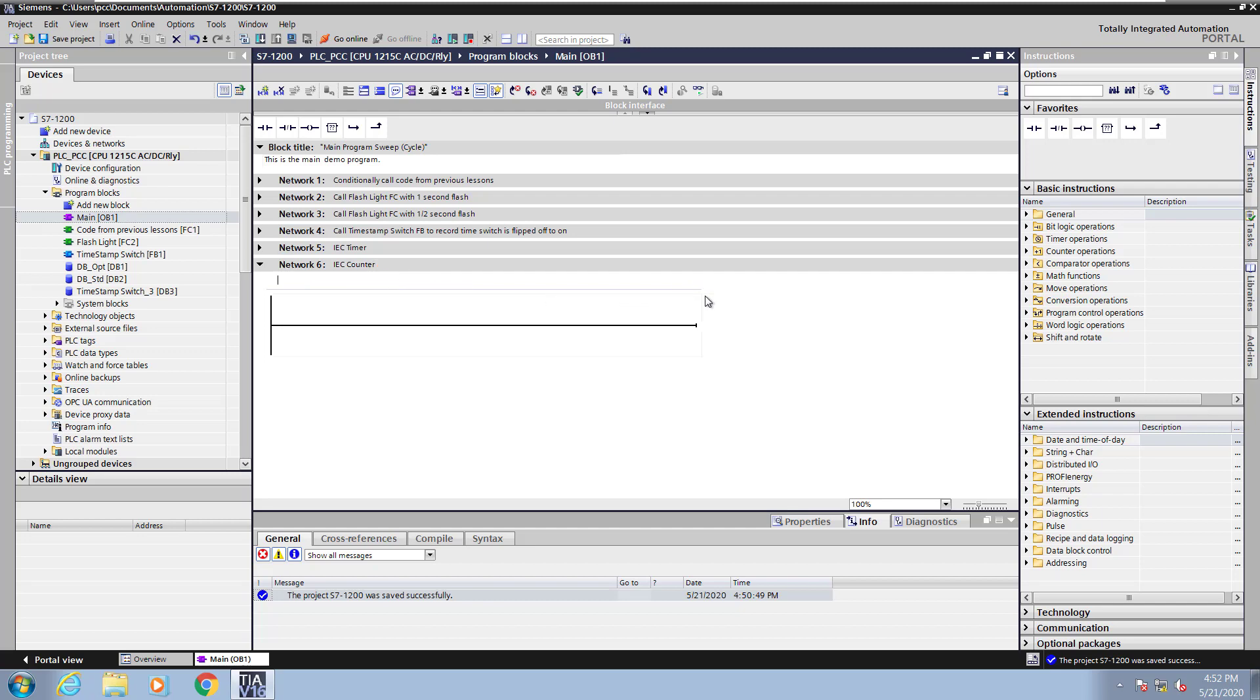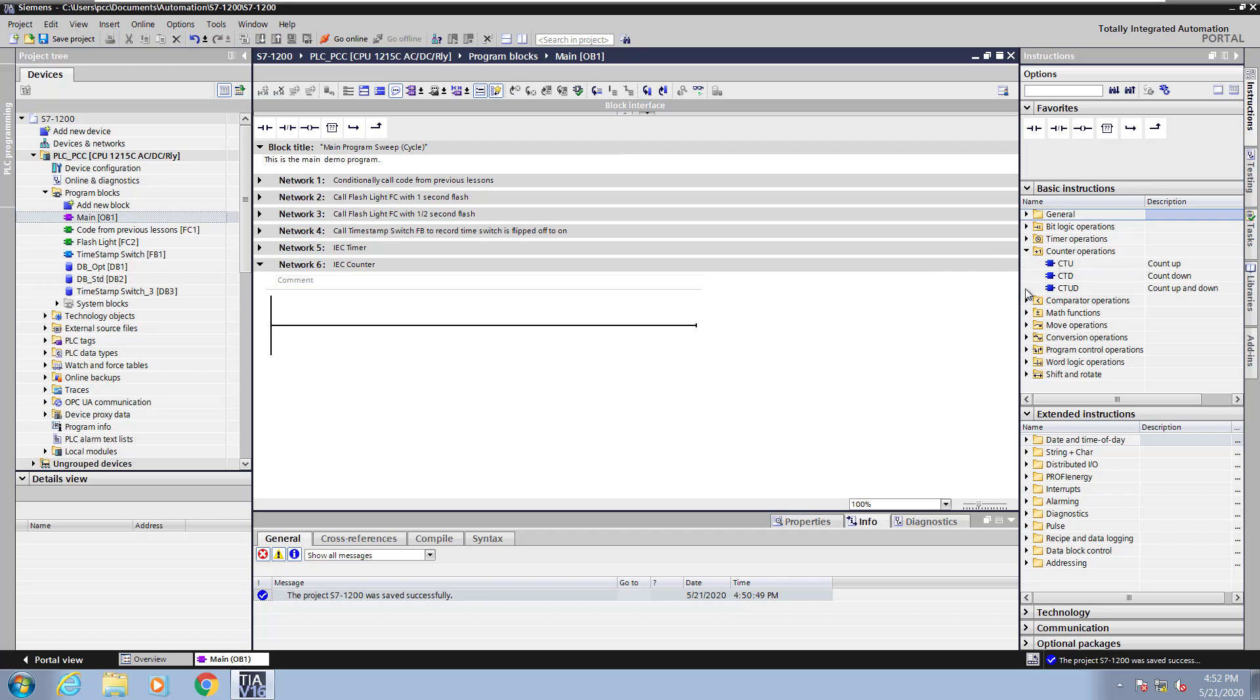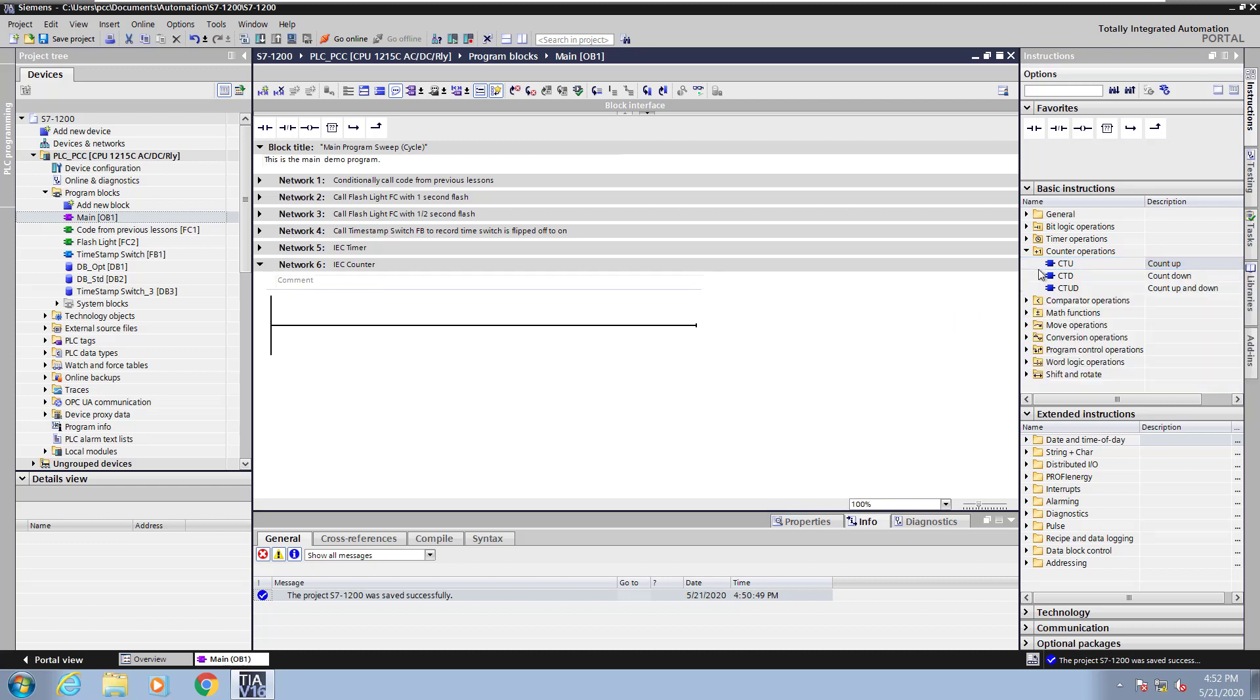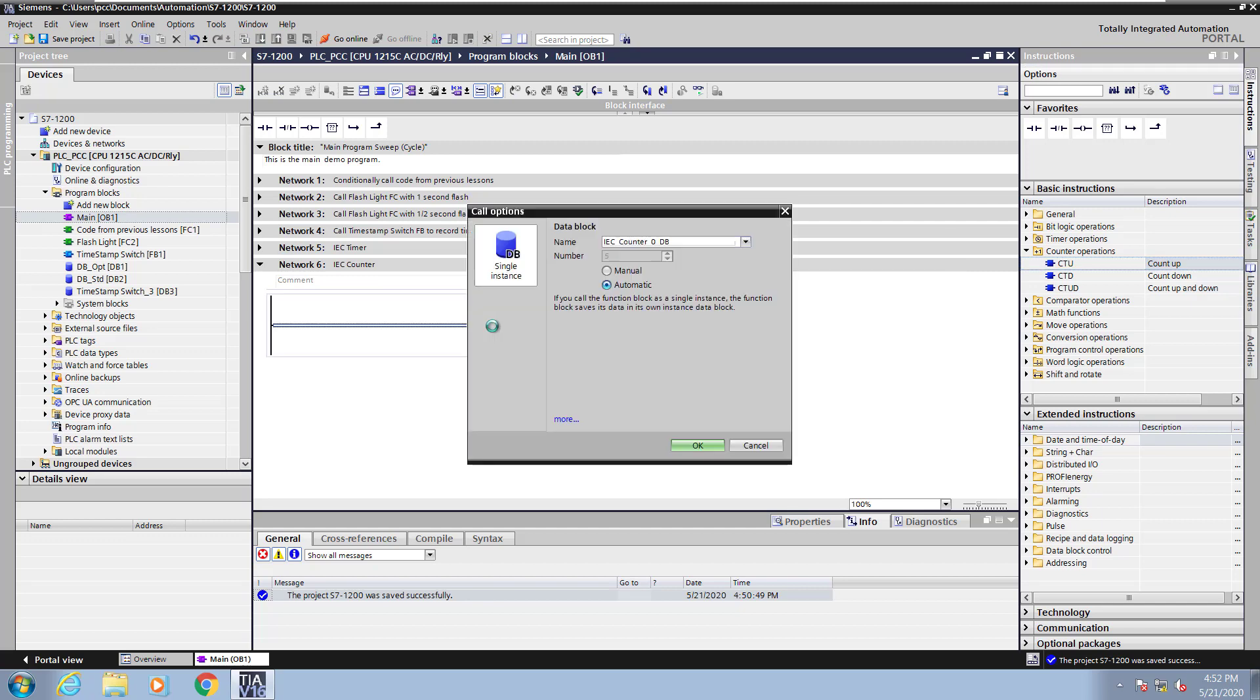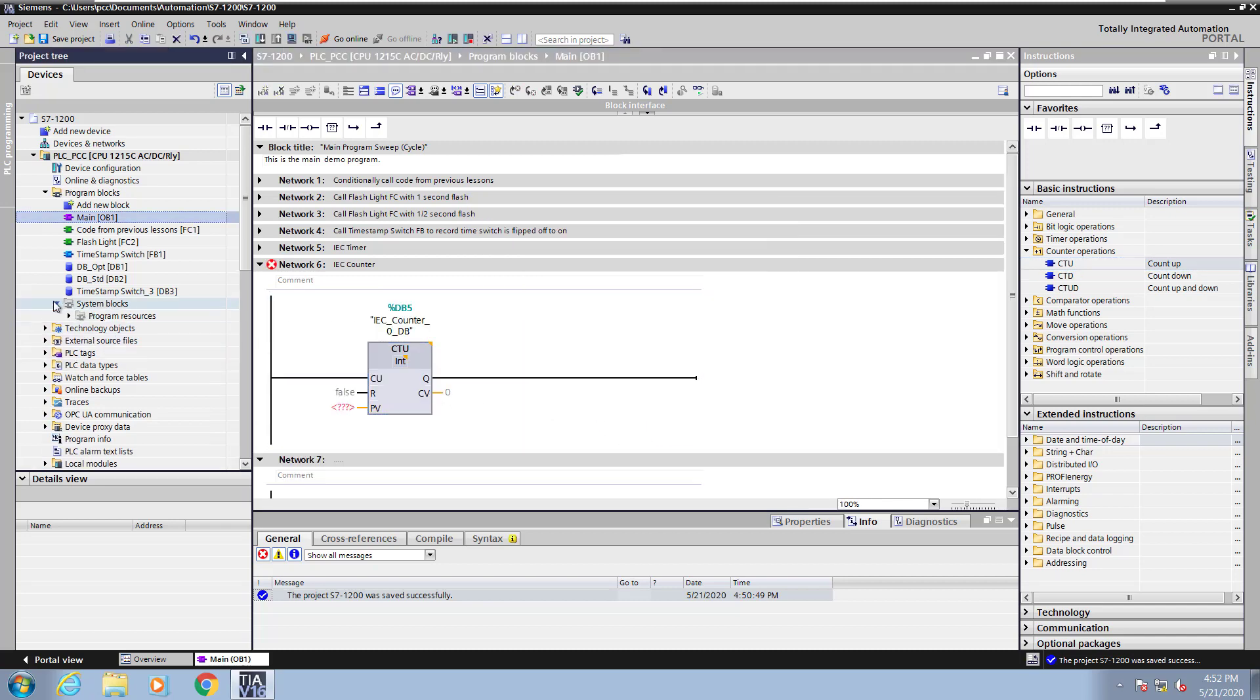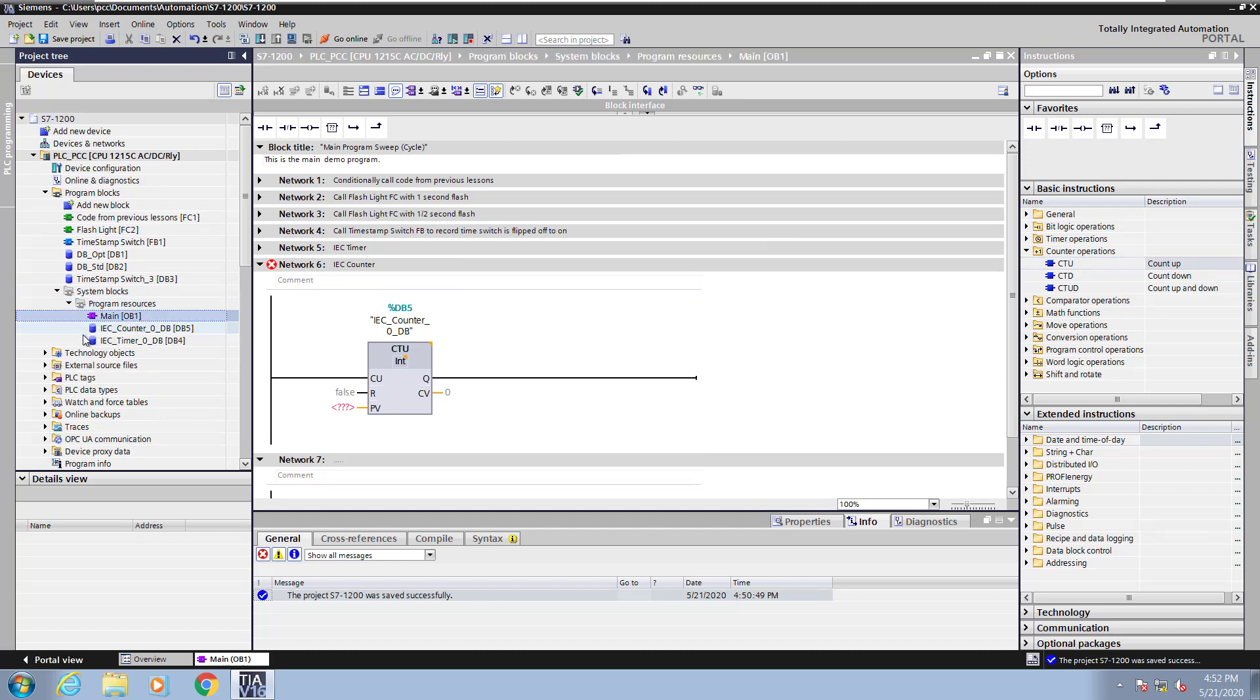In the basic instruction area I am going to expand out the counter operations. I will hover over the CTU instruction which is the count up counter. This will bring up the help for the instruction. I will drag the CTU instruction into the ladder editor and this will bring up the call options dialog box. I will do a single instance data block for this instruction and select OK.